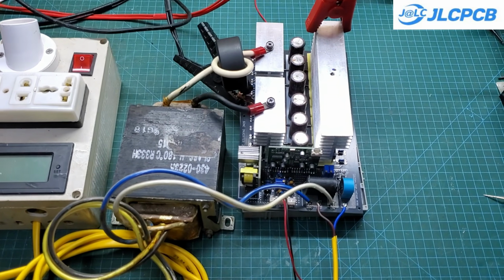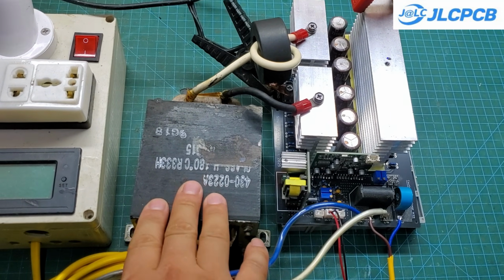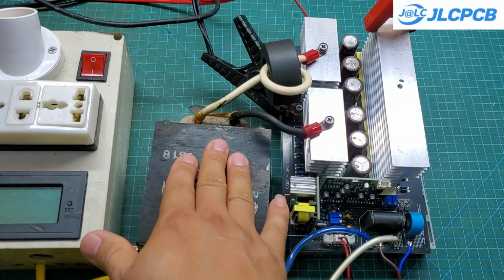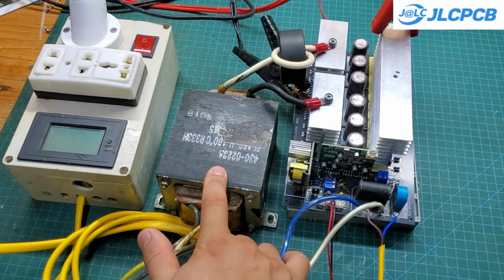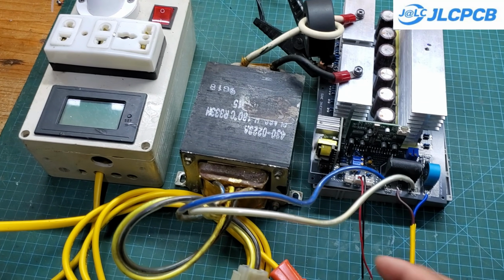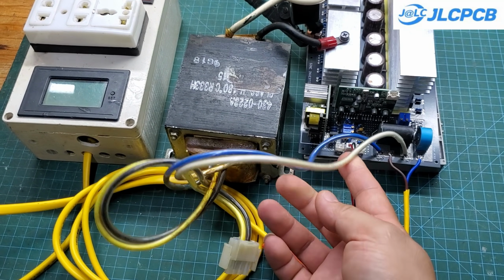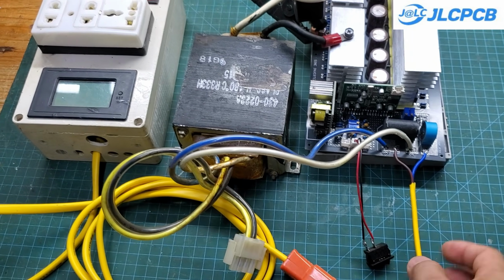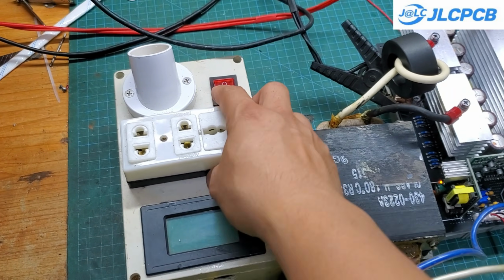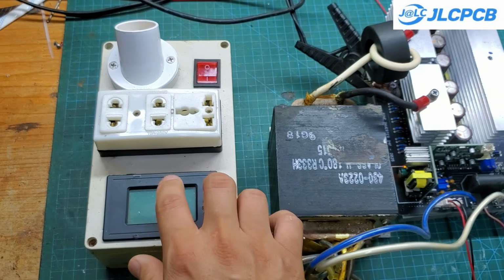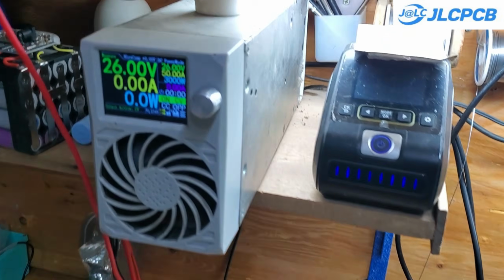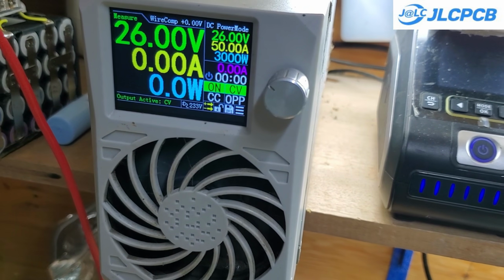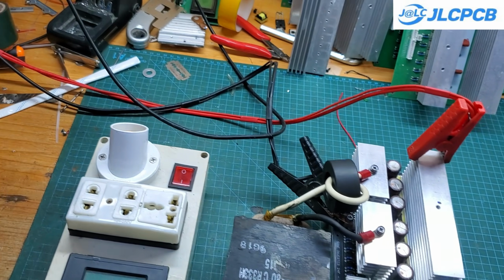At this point, I've connected the transformer's secondary winding to the circuit, and the output is also connected to a wattmeter to measure voltage and power. The input voltage for this single transformer setup is 26 volts, which corresponds to a typical 24-volt lithium battery system. As you can see, the no-load power consumption is around 17 watts, which is acceptable for an iron core transformer.